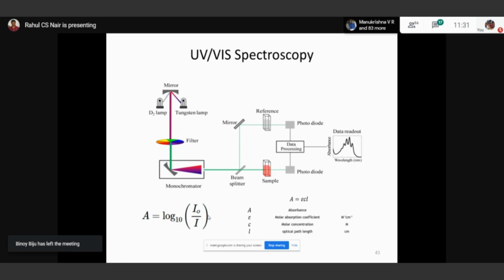Spectroscopy is basically the interaction of light with matter, and here is the simple arrangement for this instrument. There is a small light source, usually a tungsten lamp with necessary filters, and the particular wavelength can be selected by means of a monochromator. There is a beam splitter and a reference sample. The reference sample is a standard sample, and we know the concentration, so we know the absorbance value. If you put in an unknown sample, we will get some reading. By correlating this reading with the reference sample or the curve, we can determine the absorbance, and from that the concentration in the unknown sample, right?